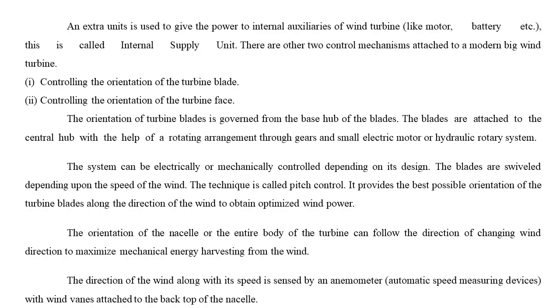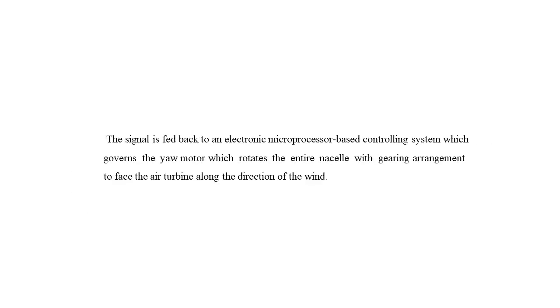The direction of the wind along with its speed is sensed by an anemometer, an automatic speed measuring device, with wind vanes attached to the back top of the nacelle. This signal is fed back to an electronic microprocessor-based control system which governs the yaw motor, which rotates the entire nacelle with a gearing arrangement to face the air turbine along the direction of the wind.